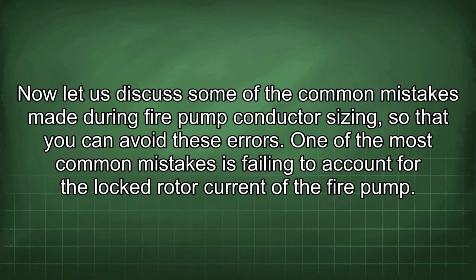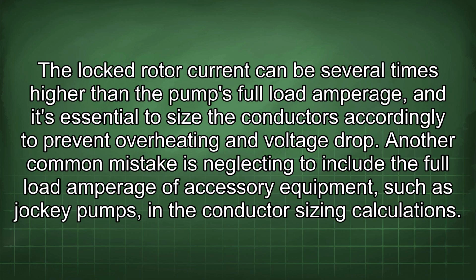Now let us discuss some of the common mistakes made during fire pump conductor sizing so that you can avoid these errors. One of the most common mistakes is failing to account for the locked rotor current of the fire pump. The locked rotor current can be several times higher than the pump's full load amperage, and it's essential to size the conductors accordingly to prevent overheating and voltage drop.